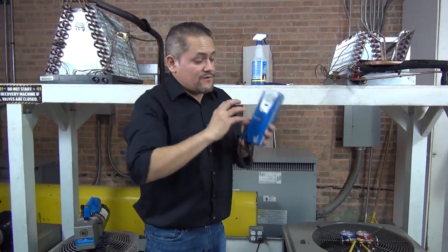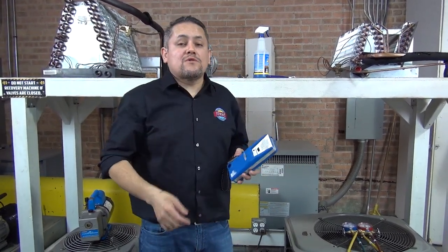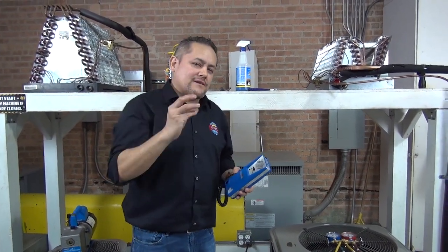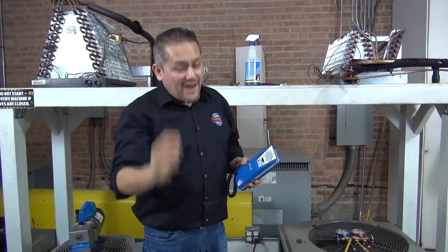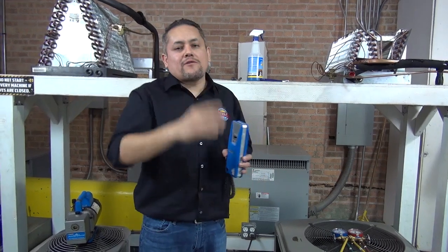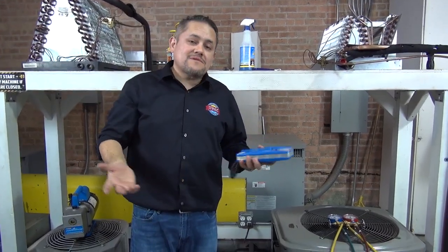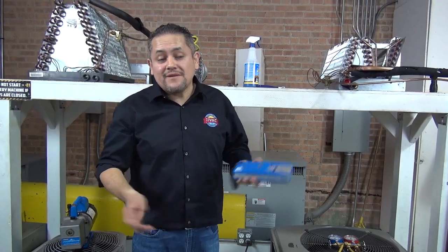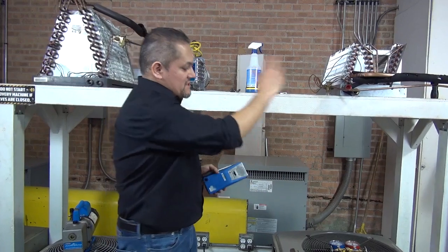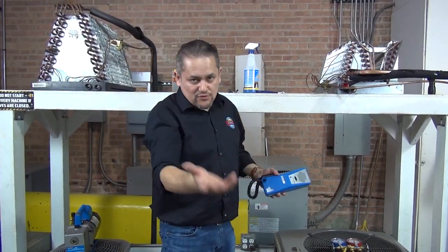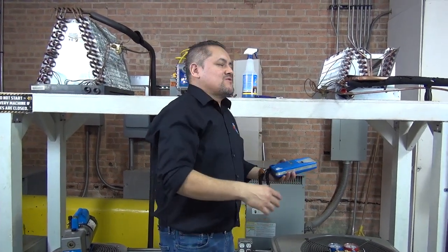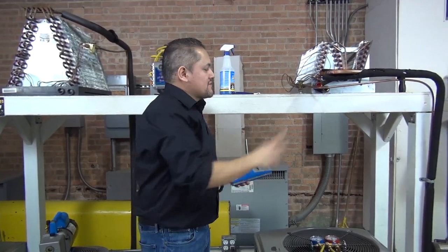Or if you cannot find the leak with this or the nitrogen, then you can use what is called ultraviolet dye. You can actually add that special ink into the system, but you have to wait 24 hours. You have to inject that special dye into the system and wait 24 hours, which sometimes you don't have the time for, or the customer wants to fix it right away. The special ink will go through the whole system, and then you come back after a day or two.